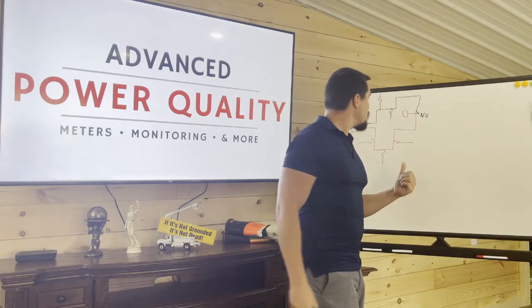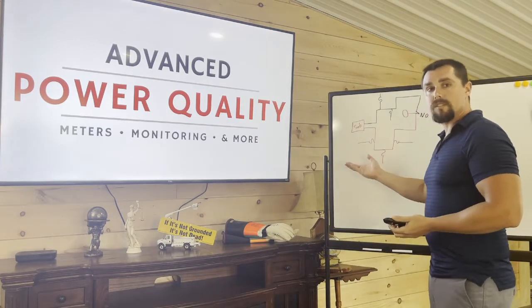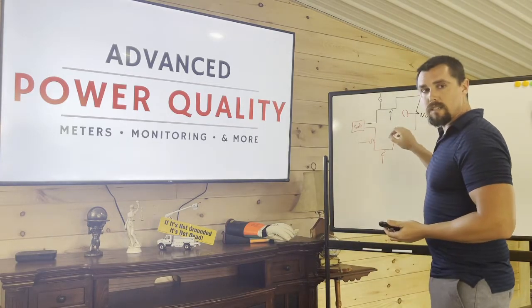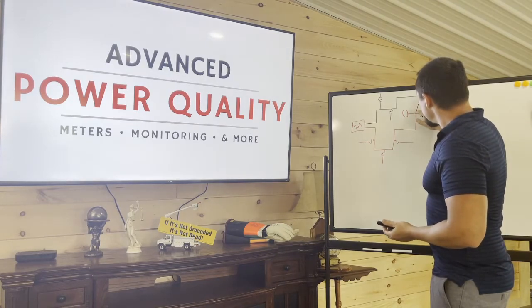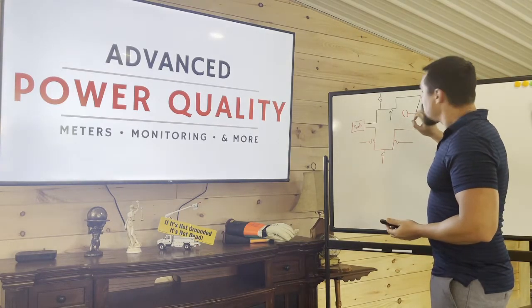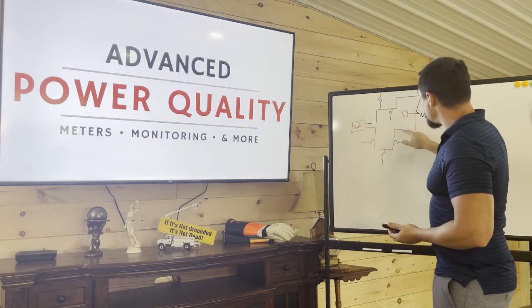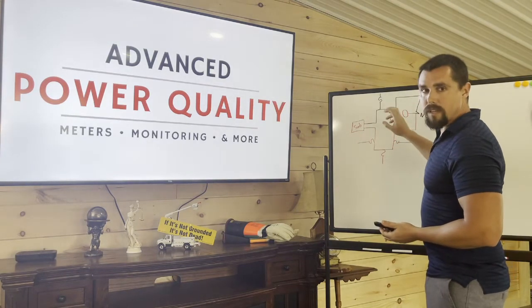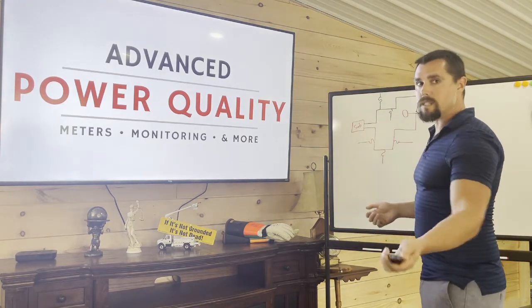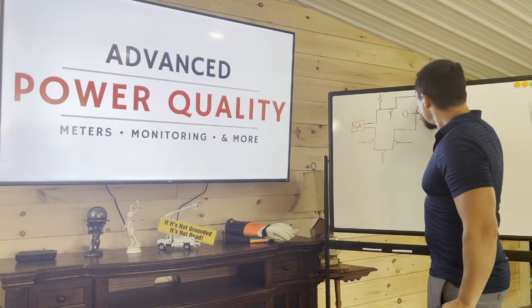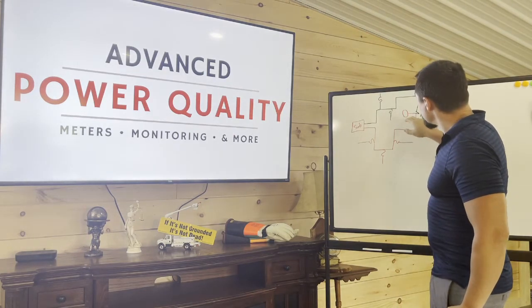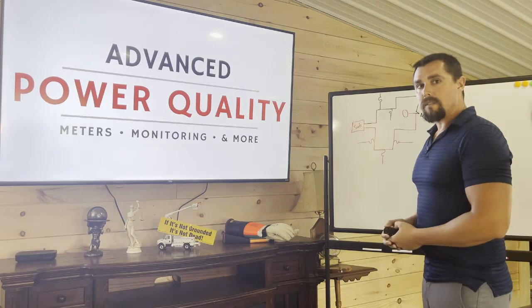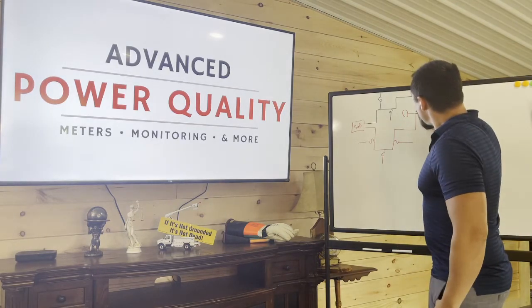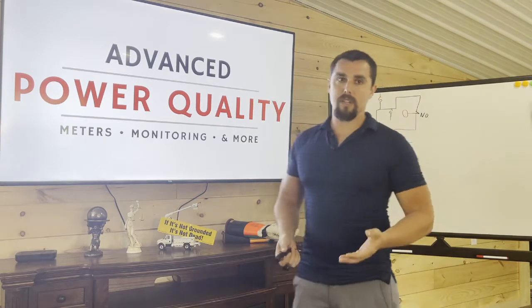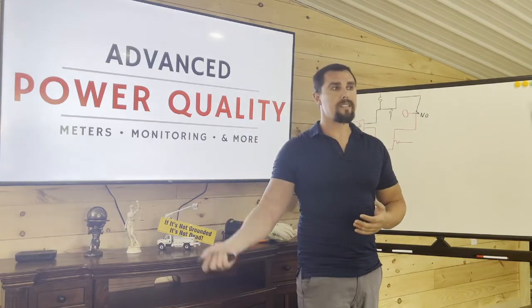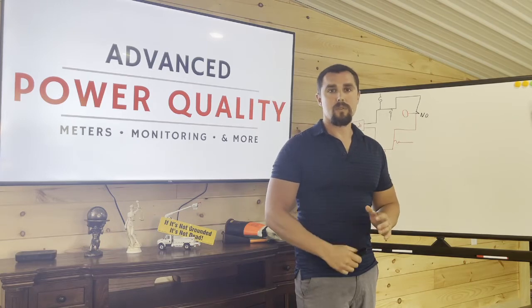As I was explaining earlier about our substation, our feeds, our ATS scheme. Regardless if you have an ATS here or not, utilities still have this normally open point, and they'll have normally open points along the feeder connecting them to several other feeders, possibly even different substations. So the utility at any given time can feed our customer from this black feed. During storm scenarios, fuses blow, outages happen, it's part of the storm.